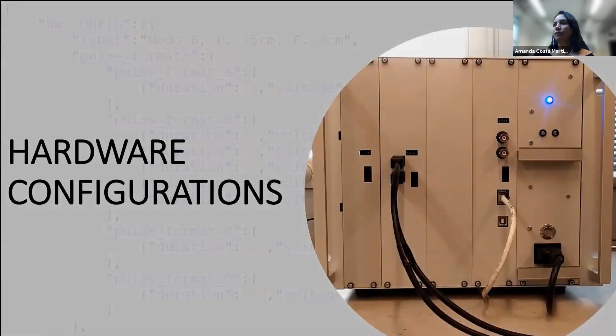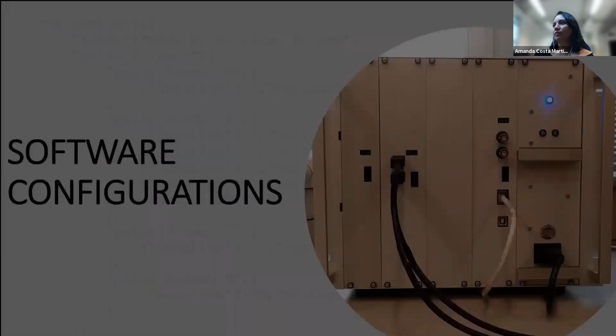So, in hardware configurations, we must configure a label, in this case, B mode with a depth of 15 centimeters and focal point at 8 centimeters. We can also configure 4 different pulse formats, A, B, C, and D. In this case, for pulse format A, we will have 70 nanoseconds in minus 24 volts and 70 nanoseconds in 24 volts. If we want to, we can add more cycles like pulse format B. We can also change the duration and amplitude of voltage like pulse format C, or like pulse format D.